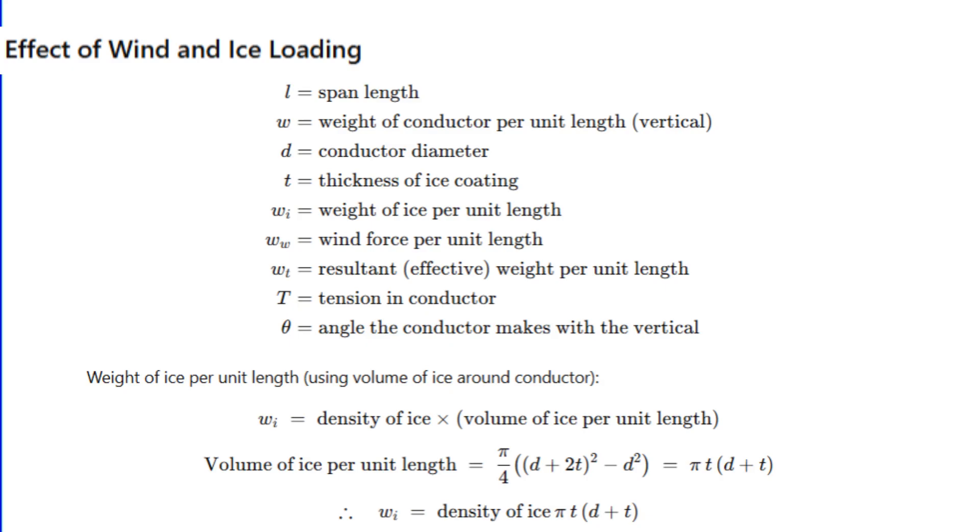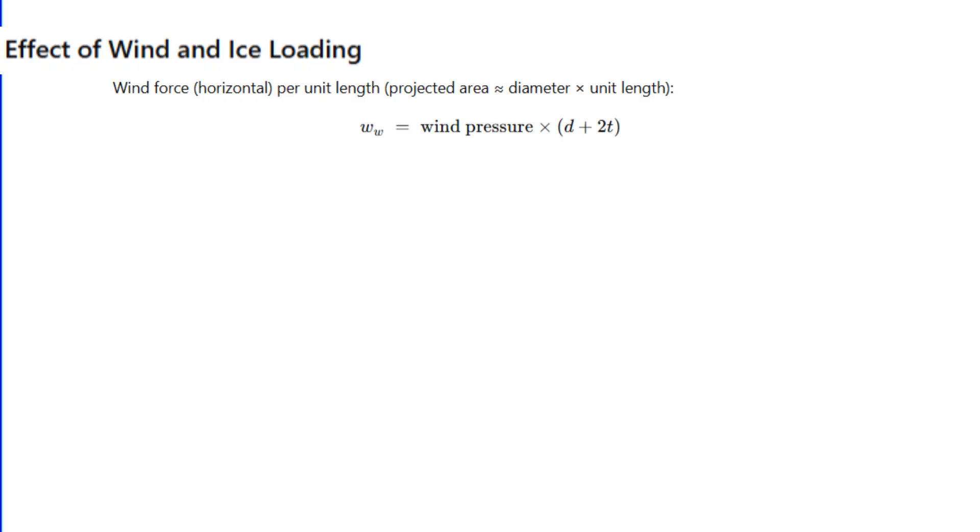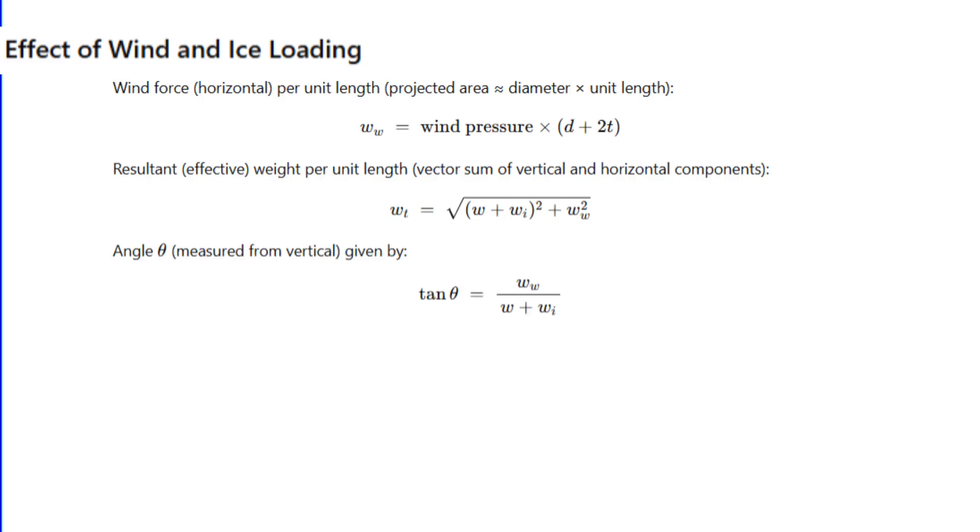The wind force per meter is ww, which equals wind pressure multiplied by (d + 2t). So the effective weight per unit length is wₜ = √[(w + wᵢ)² + ww²]. The conductor now hangs making an angle θ with vertical, where tan θ = ww/(w + wᵢ). The slant sag equals wₜl²/8T and the vertical sag equals s·cos θ.